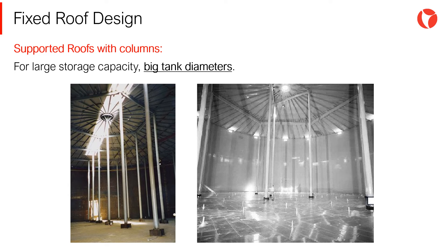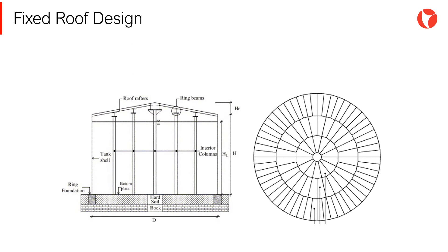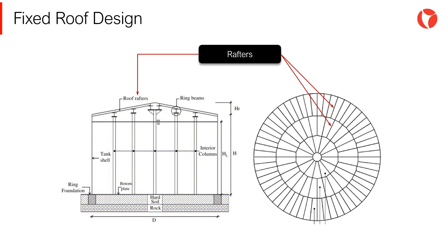Depending on the loads to be supported, columns will be located on the edges of the polygon. Beams receive the loads from the rafters and transmit these loads to the columns. The objective of the columns is to minimize the weight of the roof transmitted to the shell, reducing the cost of the structure and, more importantly, transmitting lower axial loads to the tank wall.